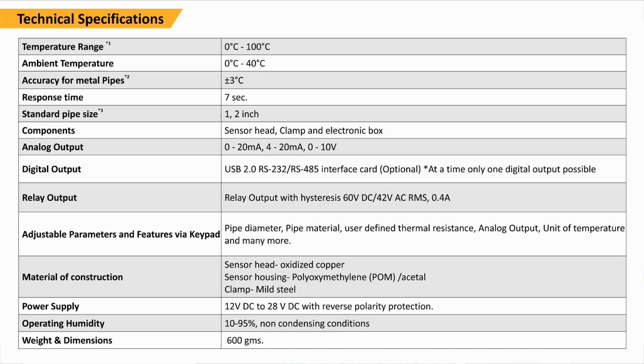There is also a relay output so that you can get an alarm. If you know that your temperature should not go over 80 degrees Celsius, it can give you an alarm signal, and then you can put a buzzer outside and keep the process in control. Adjustable parameters are also there, so you can change the pipe diameter and pipe material. These are the factors accounted for in the custom pipe functions, so any kind of pipe and any pipe thickness can be accounted for with these sensors.